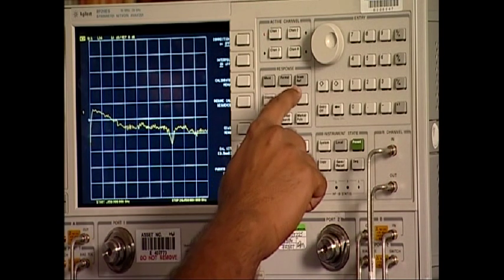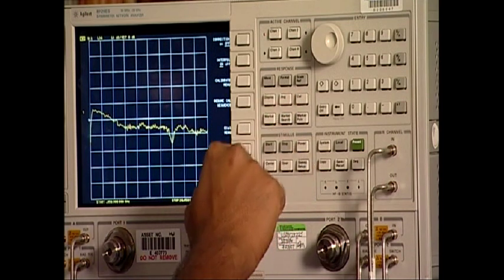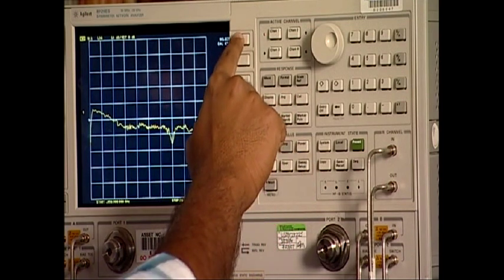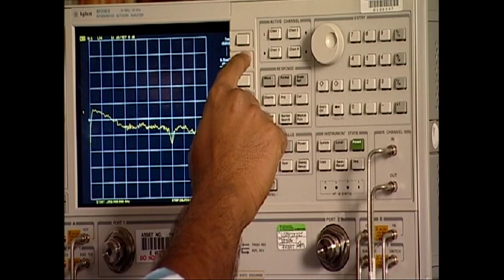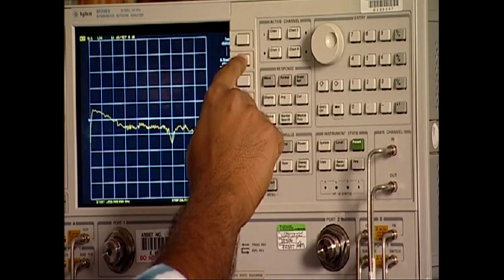We now select the calibration kit file in our analyzer. For that, we'll have to select Cal, CalKit, select CalKit and select 3.5mm d 85052, which is our calibration kit. Once we have selected the calibration file, which corresponds to the calibration kit we are using, we go ahead with the full two-port calibration.